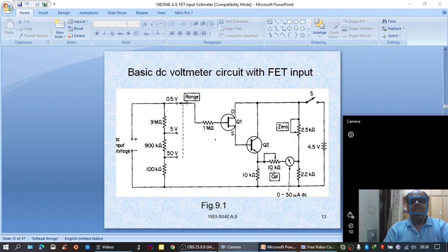Once this process is completed, you can apply any unknown input voltage here, and that can be measured very accurately, because the input impedance offered by this arrangement is very high and there would not be any loading effect, and the measurement would be very accurate. And this instrument requires 50 microamperes for its full scale deflection.